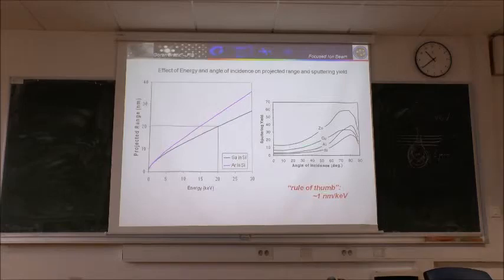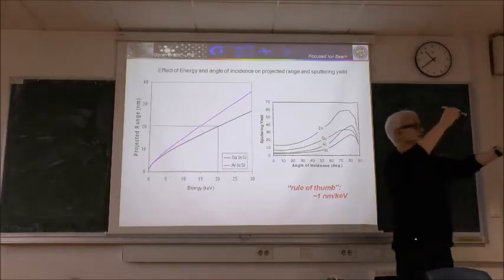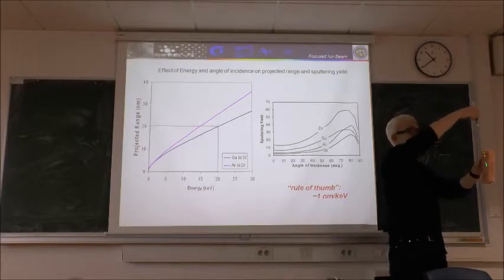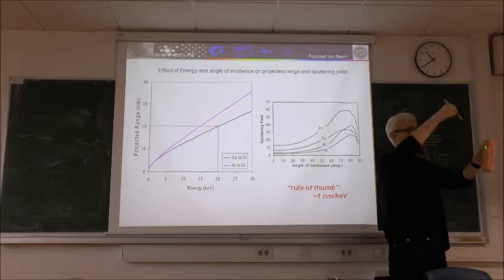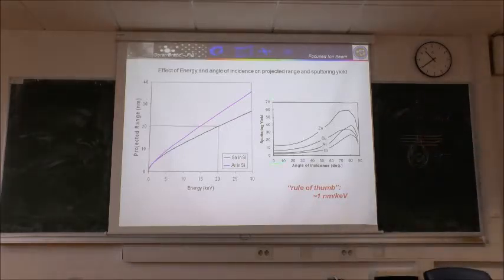Angle of incidence, that means the angle between the beam and the sample, 90 degrees, 180 which of course is parallel, does not mean anything. But this angle matters for the sputtering yield. What does sputtering yield mean? You can just imagine how many atoms you move with one ion. And we see that the maximum is something like that. Of course, at 90 degrees again, it's lowering down, but the maximum is here around 70, 80 degrees of the angle. And again, it depends on the sputtering yield of different materials. Silicon is very low, and zinc is much higher. So the rule of thumb is that 1 nanometer of destroyed, amorphous area corresponds practically to 1 kilo electron volt, which is really true.